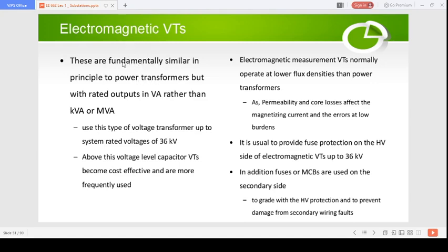So these electromagnetic voltage transformers are functionally similar to power transformers, but with rated output in VA rather than kVA or MVA. The rated power output is small compared to power transformers. This type of voltage transformer is used up to a system rated voltage of 36 kV. Above these voltage levels, capacitor voltage transformers become very cost effective, and they are used more frequently compared to electromagnetic voltage transformers.